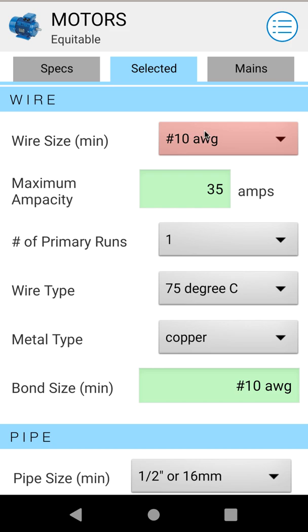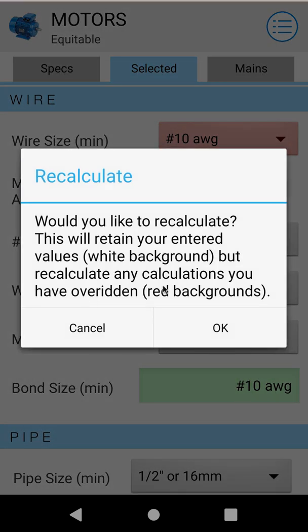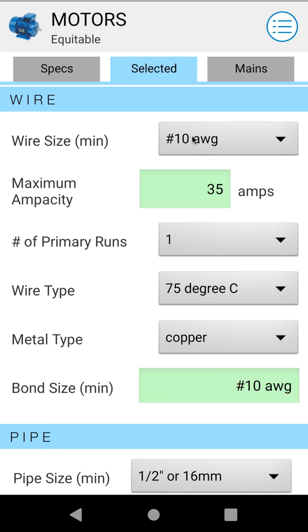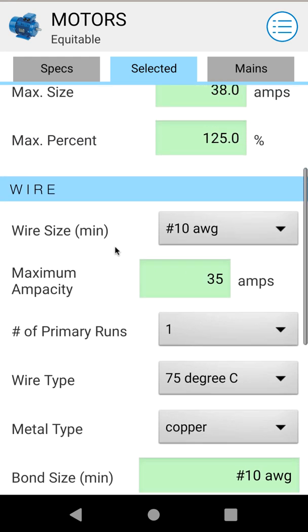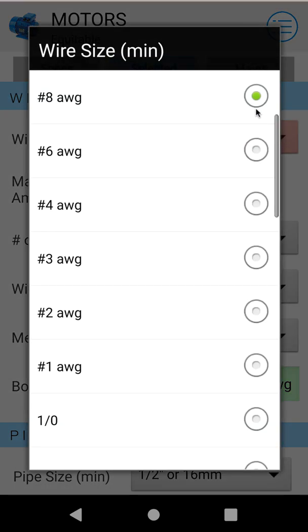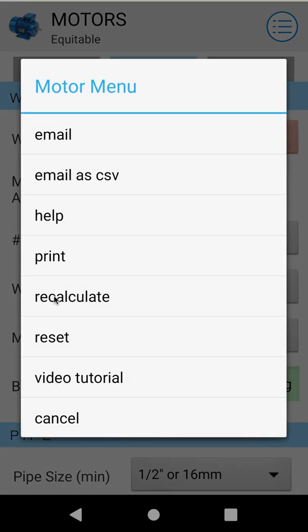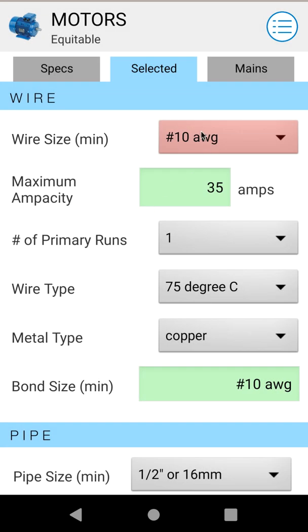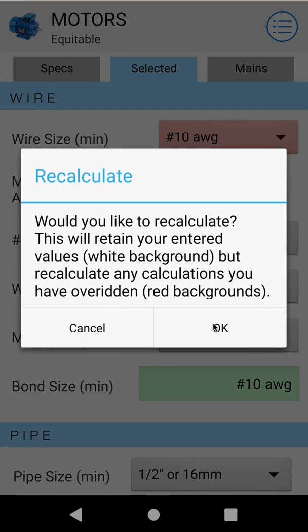Then we go down to our wire sizing. The calculated wire size right now is number 10 at 35 amp allowable ampacity. But you can always select your own wire sizing — say you want to upsize to number 8. You'll see it goes red, and all that indicates is that it's no longer a calculated value, it's an overridden value. As you override it, all your other figures will change — you'll notice now that our maximum allowable ampacity is 50. Anytime you want to get back to normal, just hit the menu, recalculate, and it will recalculate back to number 10.